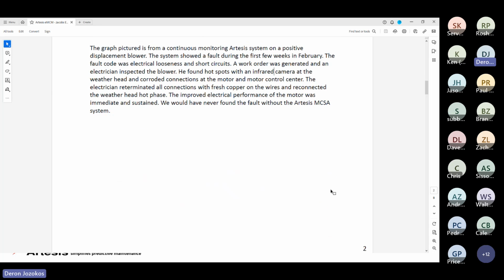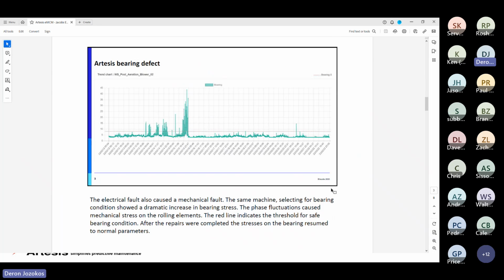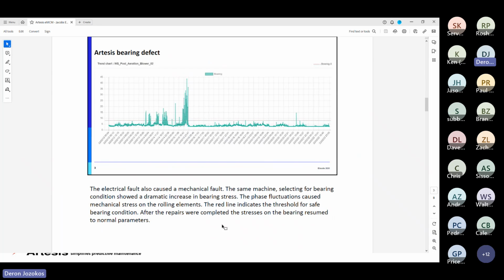Okay, not impressed yet. Let's move on to the next page. So this system, the electrical fault, also caused a mechanical fault. The same machine selected for bearing conditions showed a dramatic increase in bearing stress. The phase fluctuations caused a mechanical stress on the rolling elements. It manifested a mechanical issue.